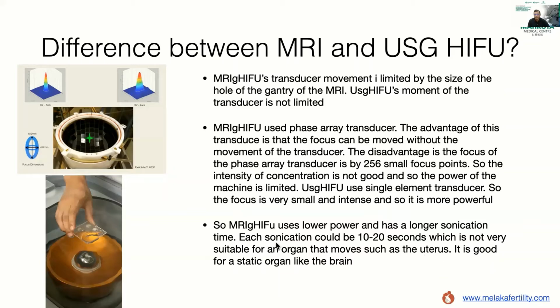But it is not good for the uterus, because when we do ultrasound-based HIFU, the sonication time is actually 1 second. We can go 1 second by 1 second. The most we do is 2 seconds. So we can have very, very controlled ablation with the ultrasound-based HIFU. That's the reason why the MRI-based HIFU did not really succeed very well for uterine fibroid and adenomyosis.